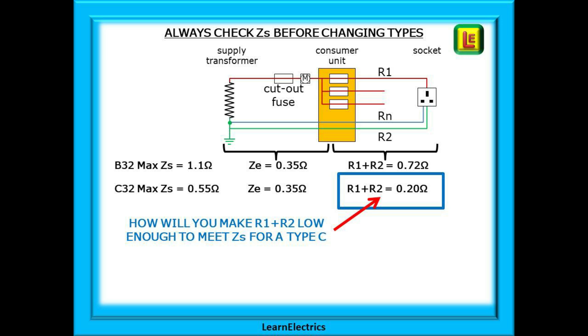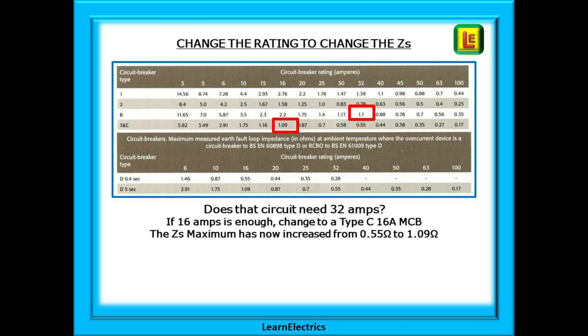You are never going to achieve this unless you move the machine next to the consumer unit. There is however another solution. Does that particular circuit actually need 32 amps? So very often a 32 amp circuit is installed as standard just because 32 amps is always installed. But what if the machinery only needed 13 amps? Could we install a C16 MCB instead and not alter any of the wiring?